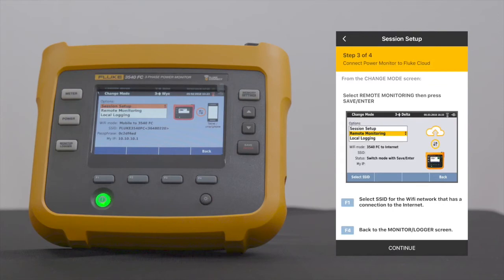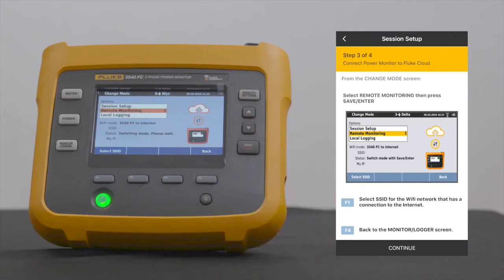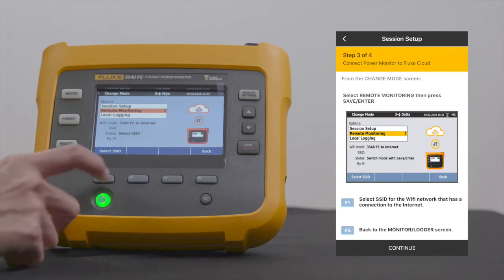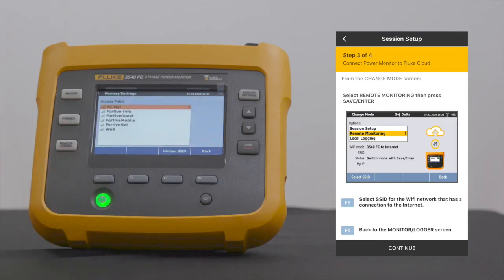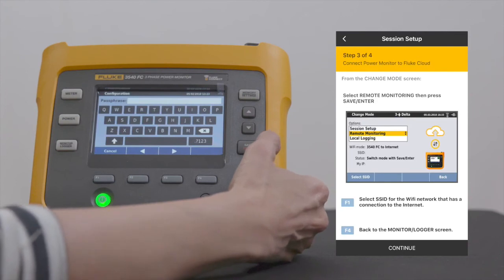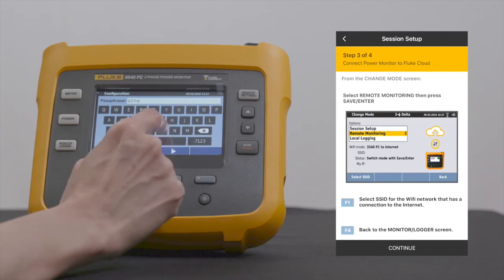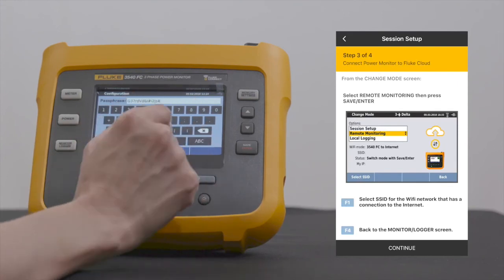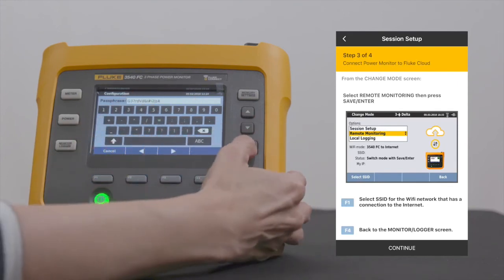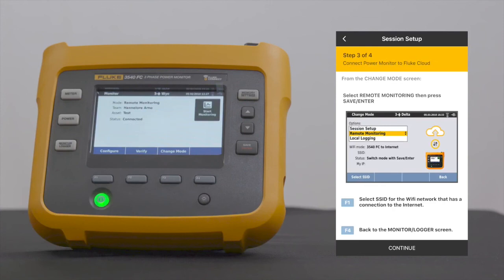On the Power Monitor from the Change Mode screen, use the arrow buttons on the right to select Remote Monitoring, then Save and Enter. Press F1 to select SSID. If a password is required to connect to your selected SSID, this screen will prompt you to enter it. After entering the password, select Save and Enter. This is when the Power Monitor initiates connection to the cloud. Then press F4 to go back to the Monitor Logger screen.